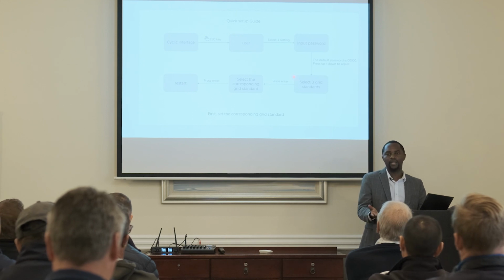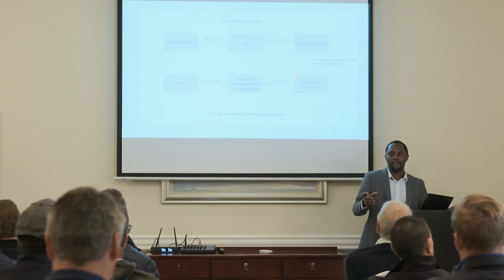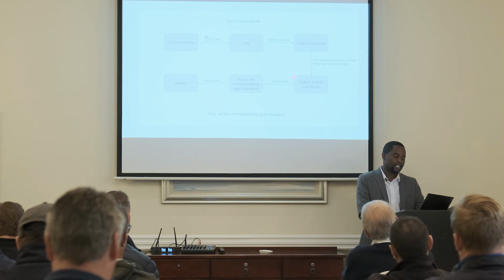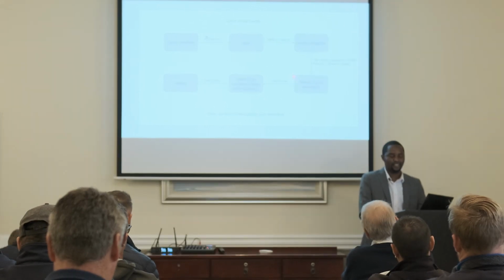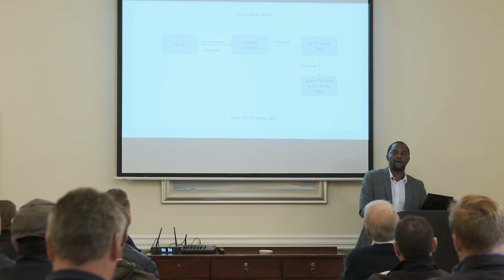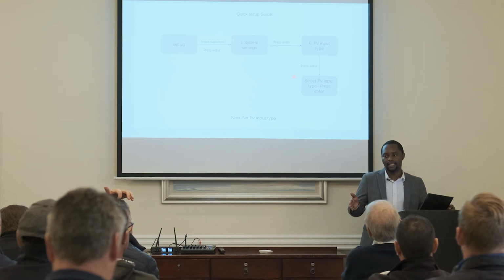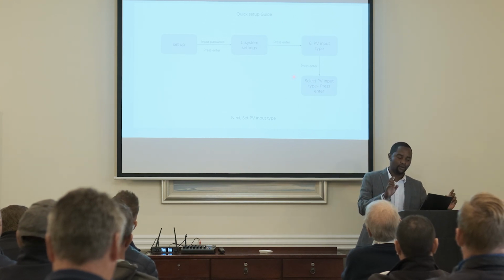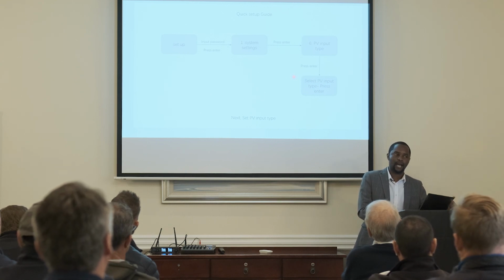So at least the security is password protected, but for you to access this setting, you need to know that it's 5 zeros. If you're looking at it for the end user or any other person, definitely I don't think they can crack 5 zeros. Right, so what you need to check on the PV, you don't need to set anything, but the inverter has got a functionality. Let's say you parallel your strings from the outside, then you wire them on one string input and blank the other string input. You can actually come and tell it and configure that you have got a high amp string that is coming. Then you can set that.